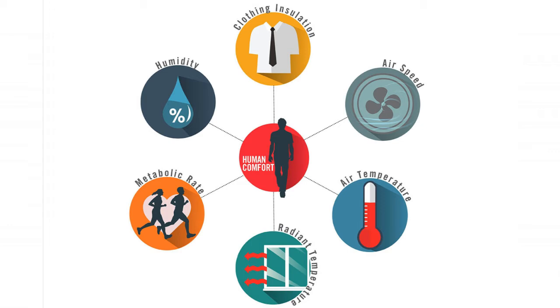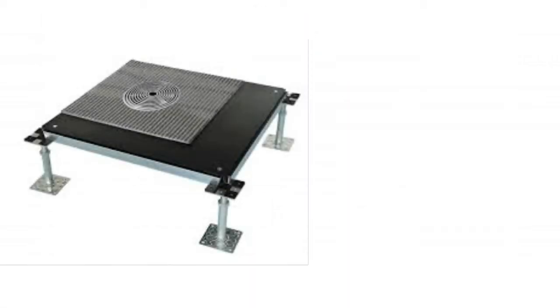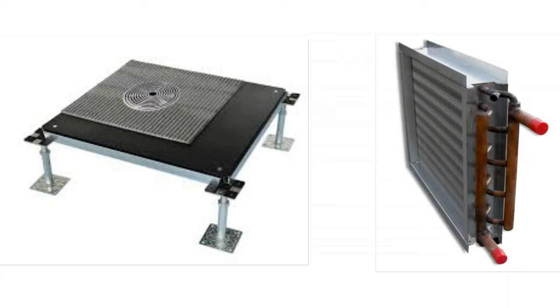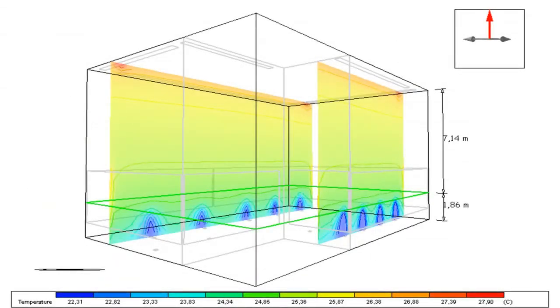Analyzing the project requirements and trying to fulfill all the comfort needs of the occupants, we decided to implement a sophisticated and elegant solution to meet the demands. We started out with a classic underfloor air distribution system. By developing the idea further, the solution was completed with the zone reheat terminals. The UFAD provides isothermal environment in the occupied zone, which is also confirmed by the air distribution efficiency equal to 1.0. Therefore, another temperature zone takes shape in the ceiling area, which is warmer.